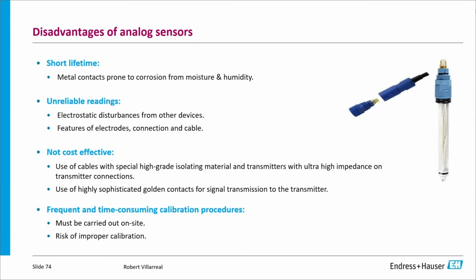So traditionally, some of the limitations of analog probes that we have corrected with this technology are exposed metal pins that may be prone to corrosion, depending on the environment or moisture ingress, signal noise or ground loop issues that you may run into on the electrical connection, complex wiring or additional preamps and power to isolate the sensitive millivolt signals. And the last major limitation of traditional analog sensors for online analysis is that they have to be connected and calibrated in loop with the transmitter to do a field calibration, which is sort of a limitation. Next slide, please.